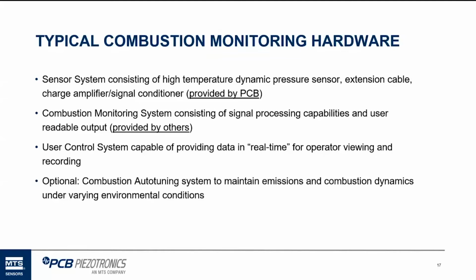From there, and we don't have these next products, but they're combustion monitoring systems. So there's several companies out there that make this system. That takes the output of our sensor system, does all the signal processing and gives all the outputs, and also connects to potentially an auto tune system. And if you don't have that, there's no need to have a sensor system. So we provide the sensors to most companies that provide the combustion monitoring system, the data collection system, if you want to call it, or DAC.